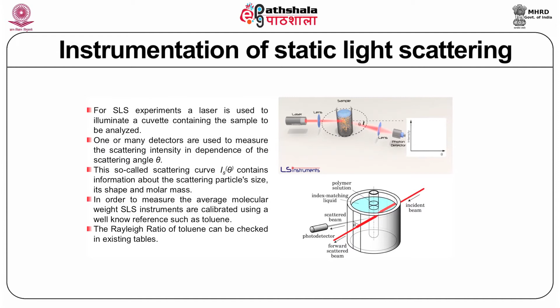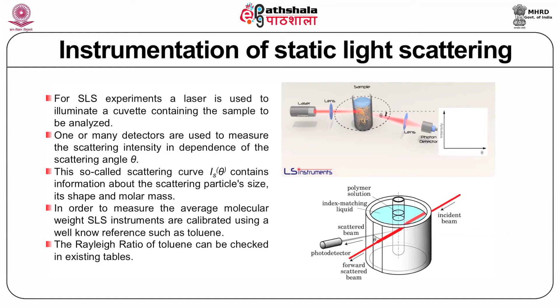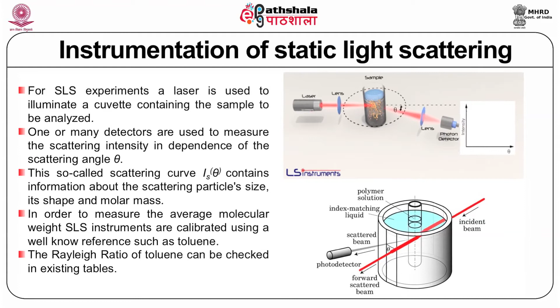So, for an SLS experiment, a laser is used to illuminate the cuvette containing a sample to be analyzed. One or many detectors are used to measure the scattering intensity in dependence of the scattering angle, that is theta. This so-called scattering curve, that is I(theta), contains information about the scattering of the particle, its shape and its molecular mass of course. In order to measure the average molecular weight, SLS instruments are calibrated using a well-known reference material such as toluene, and the Rayleigh ratio of toluene can be checked from existing tables.